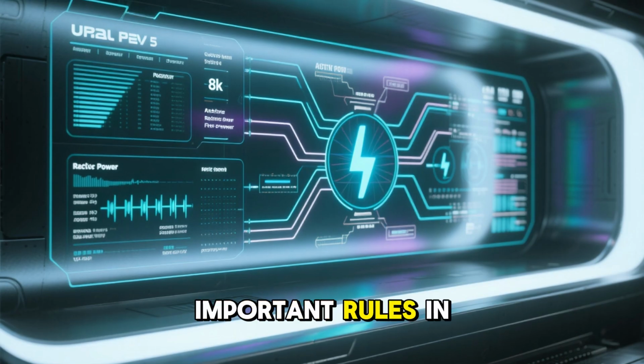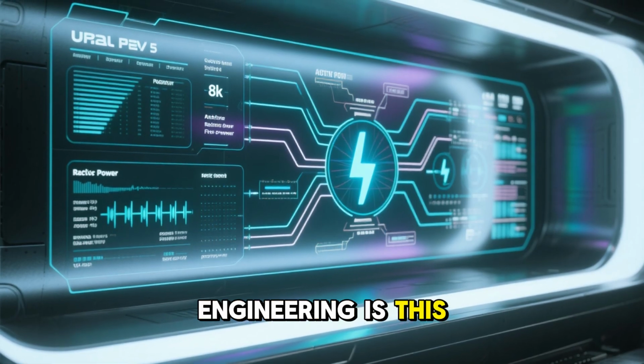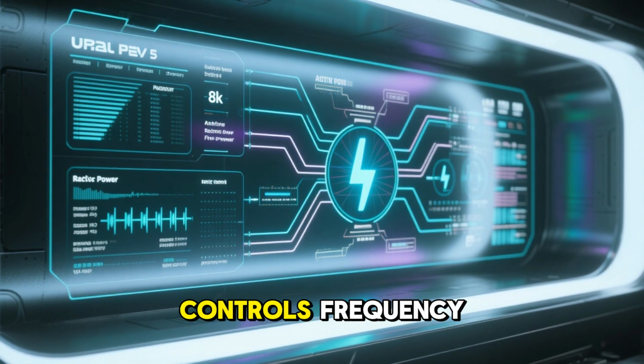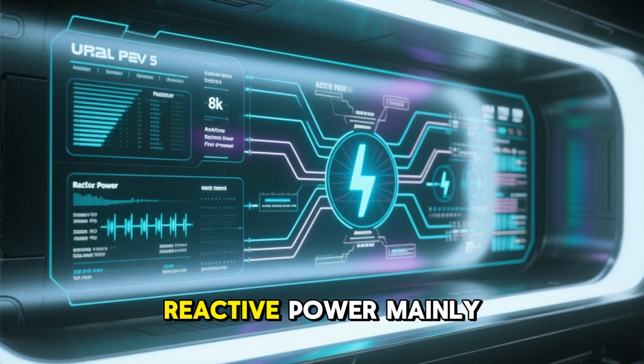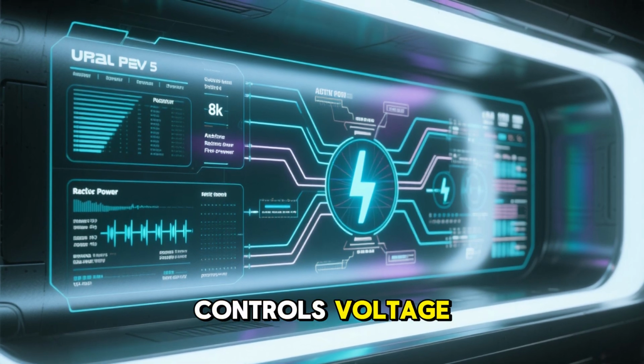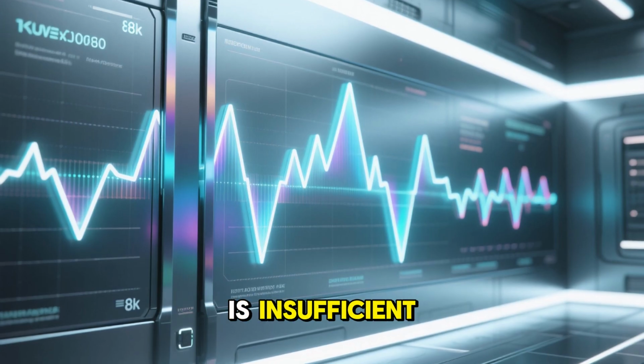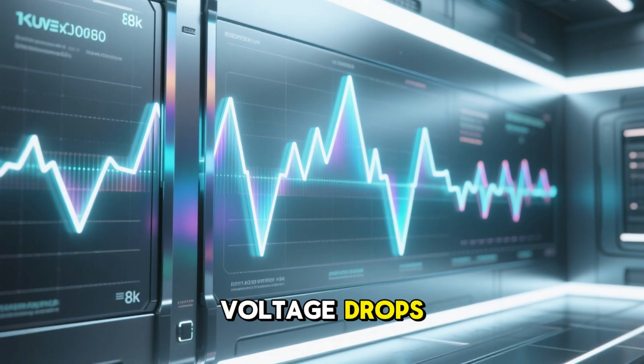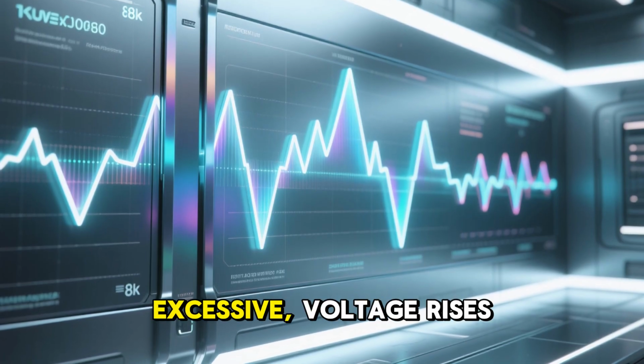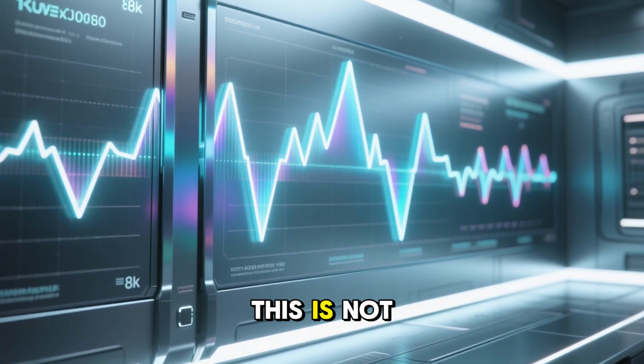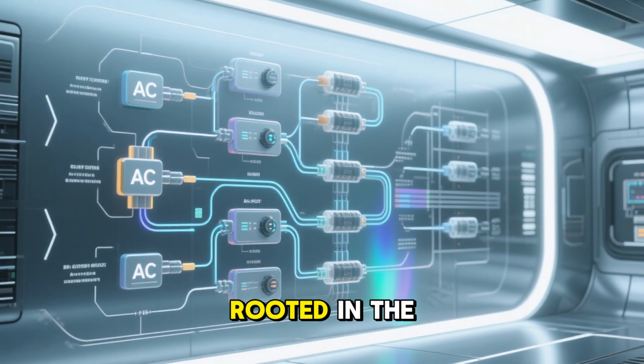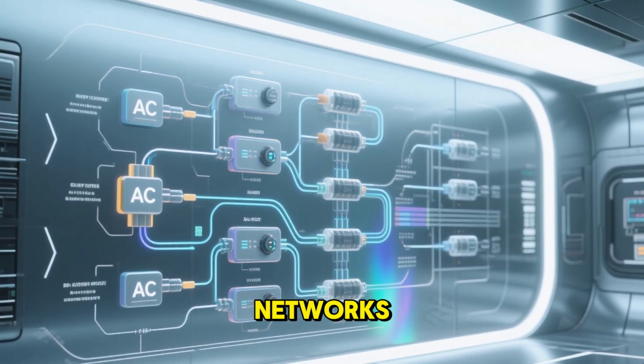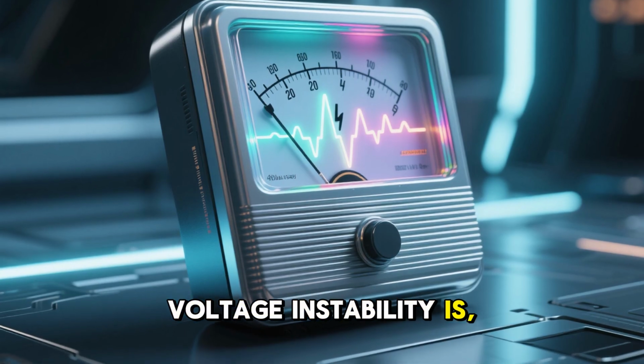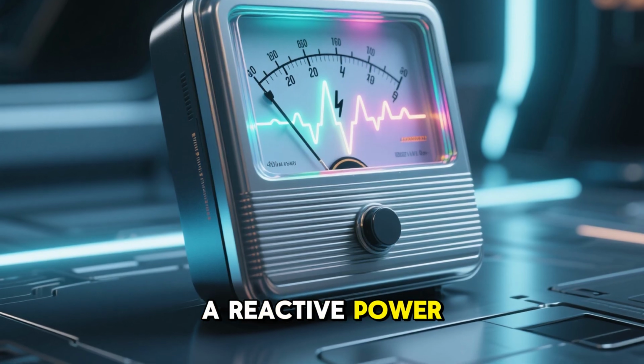One of the most important rules in power system engineering is this: active power mainly controls frequency, and reactive power mainly controls voltage. When reactive power is insufficient, voltage drops. When it is excessive, voltage rises. This is not a coincidence. It is deeply rooted in the physics of AC networks. Voltage instability is, at its core, a reactive power problem.